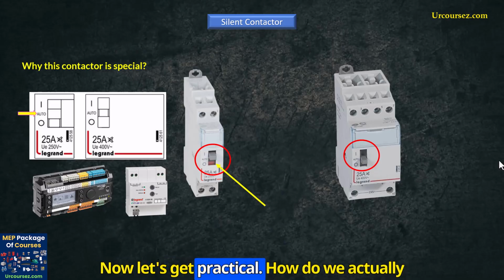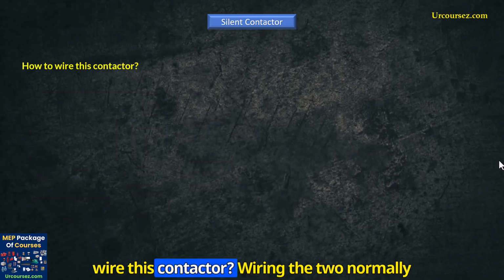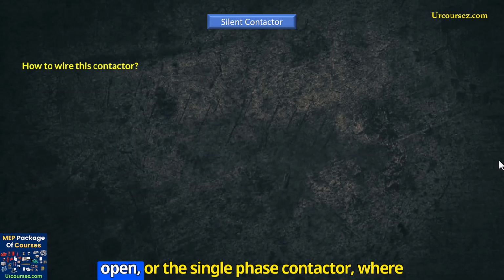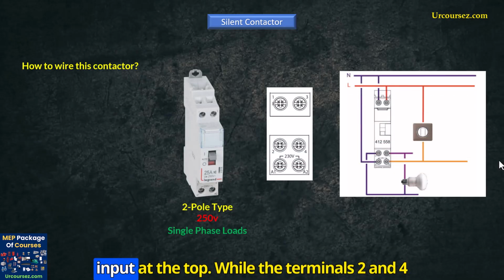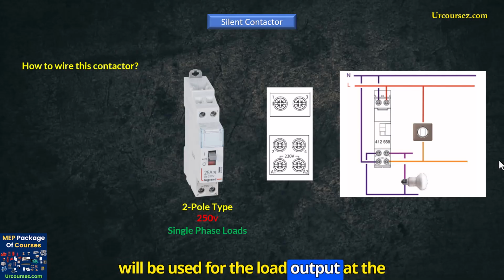Now let's get practical. How do we actually wire this contactor? Wiring the 2 normally open, or the single-phase contactor, the terminals 1 and 3 will be used for the line input at the top, while the terminals 2 and 4 will be used for the load output at the bottom.